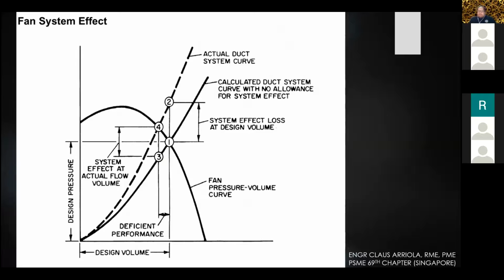Okay, fan system effect. Fan system effect is the effect of the system on the actual volume of your fan, or the actual design system curve of your fan. Of course, you need to consider what is the calculated system design volume, and then what is the actual design volume. Okay, so when you're selecting your fan, you need to know what the system curve is, which mostly suppliers will guide you on.